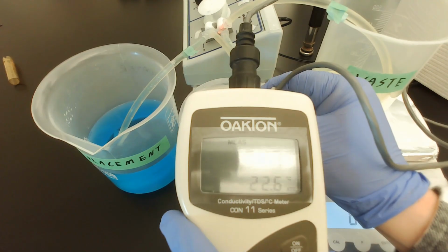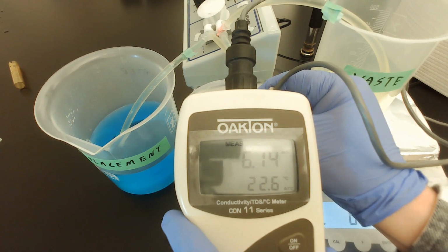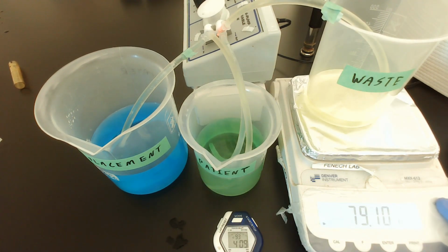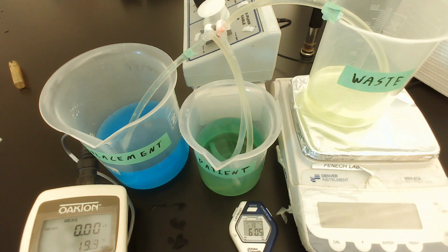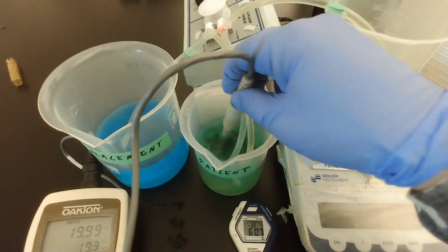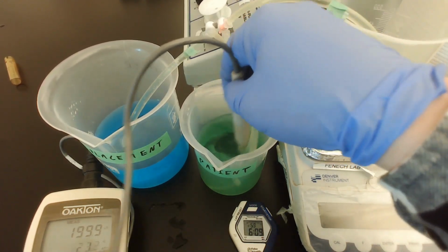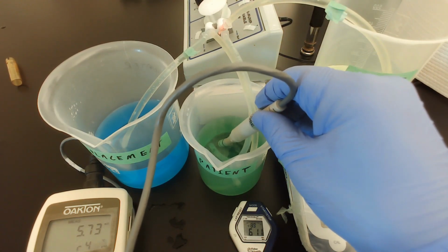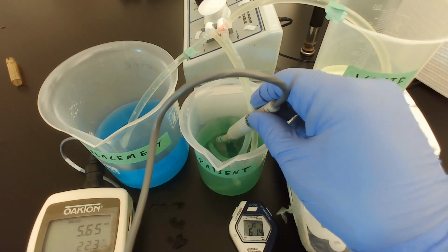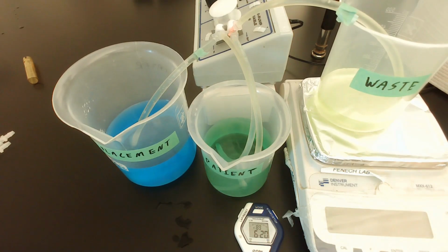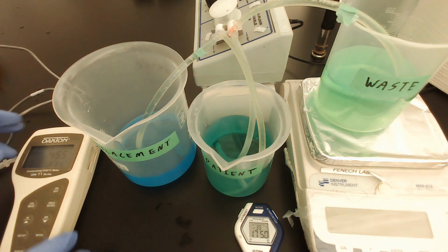And so now, after 3 minutes, we're also going to take a measurement of the conductivity of our patient, and you'll notice it has gone down from the roughly 8 millisiemens that it was before to 6.2. And again, every time we take a conductivity measurement, we want to make sure the patient's solution is mixed very well, just to ensure that the salt hasn't settled. And we'll continue to do this throughout 20 minutes.